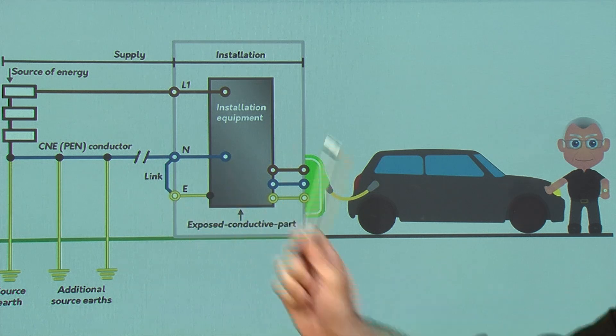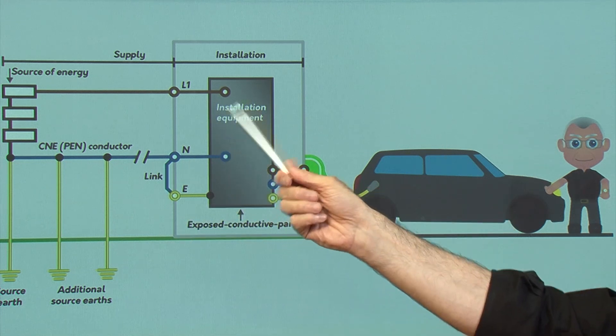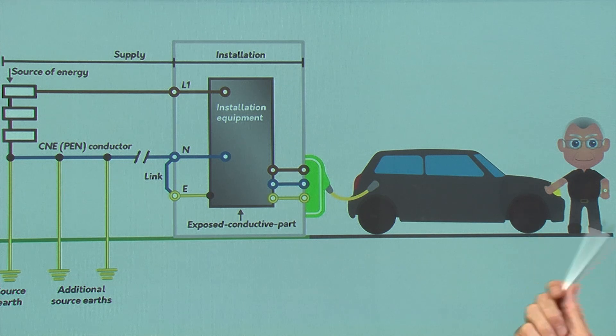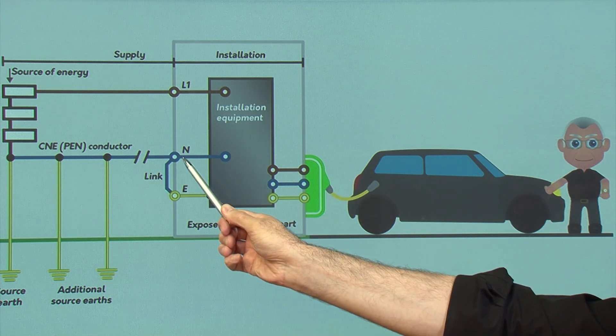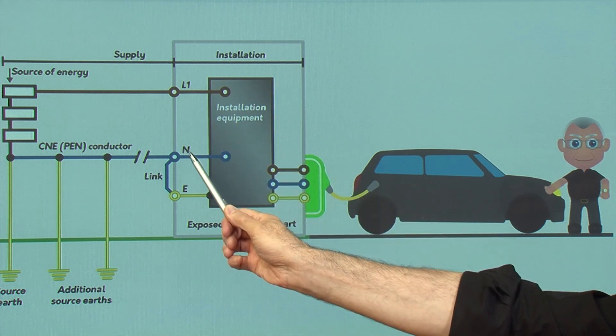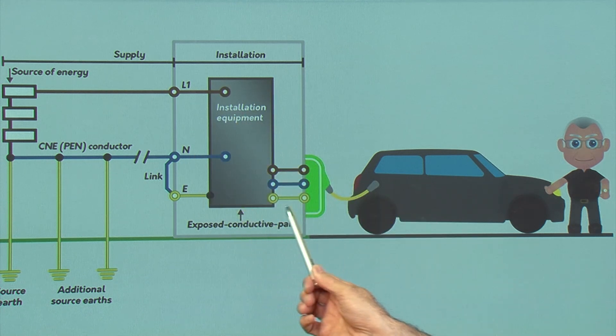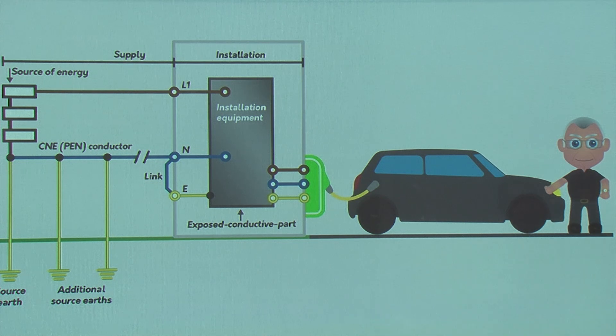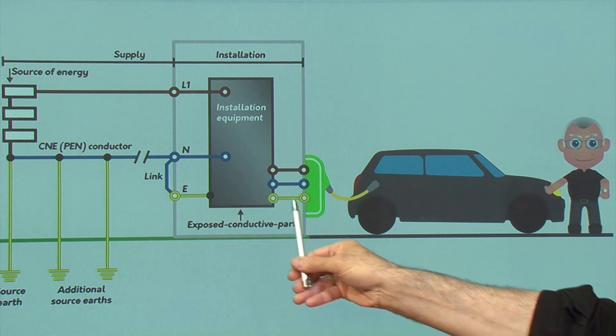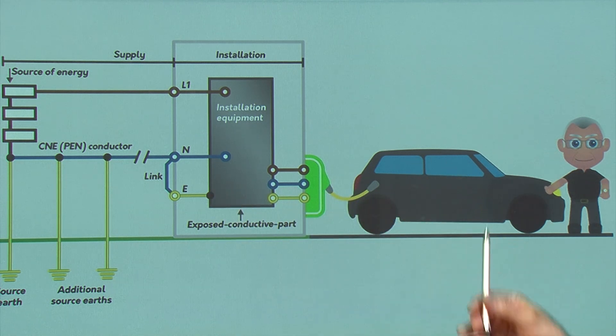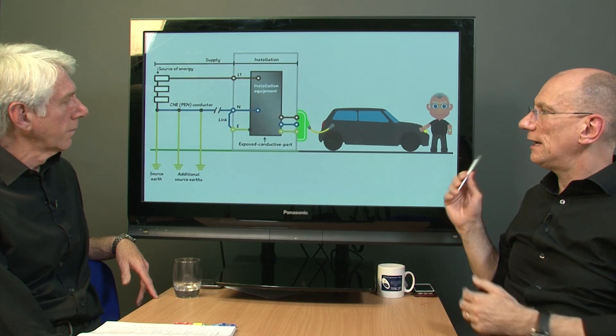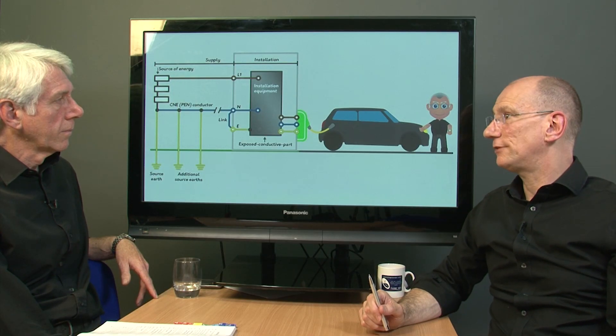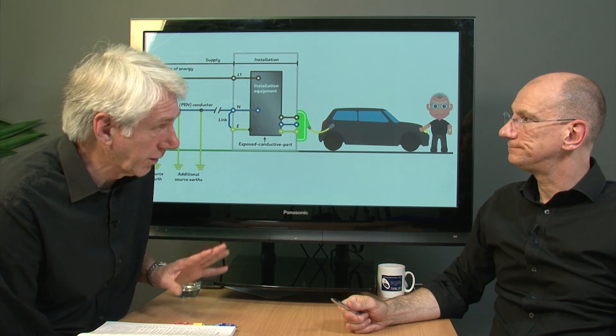So if you end up with a broken neutral, the return path will look for an alternative way to get back. And what it does is it comes back to the neutral point in the installation, and there's a link there to the earth. It will try and find an alternative path. And if you've got gas pipes, water pipes, it will try and go down there. But in this particular case, we've exported it out through to this vehicle. So if you've got a person in contact with that vehicle and touching earth, this will be a raised potential, and you are at risk of electric shock, which could be fatal. So there's the problem that the regs are trying to sort out.